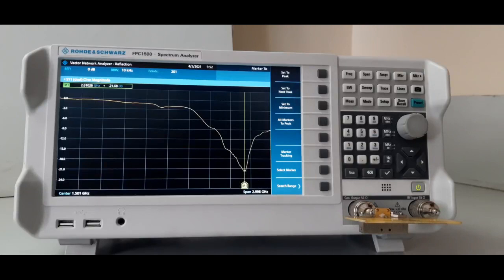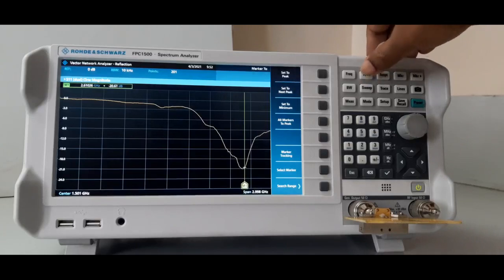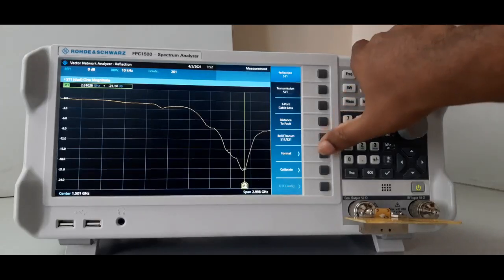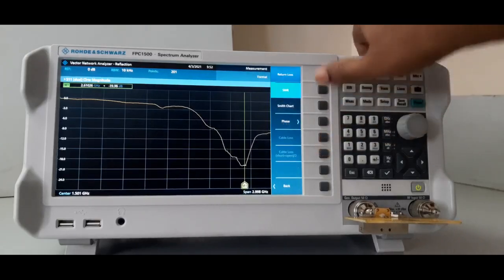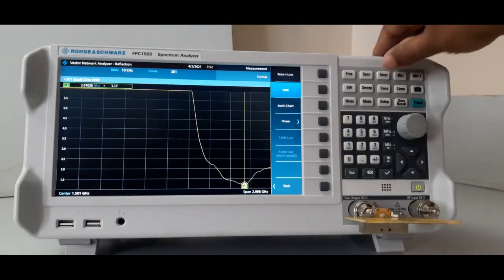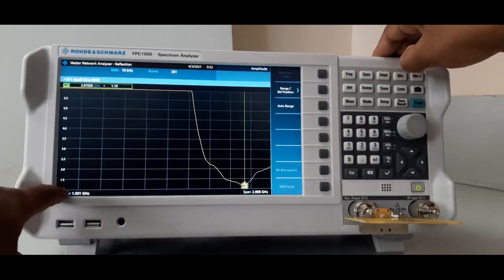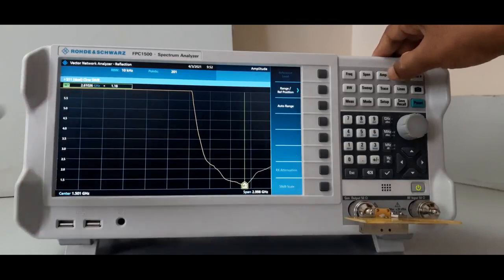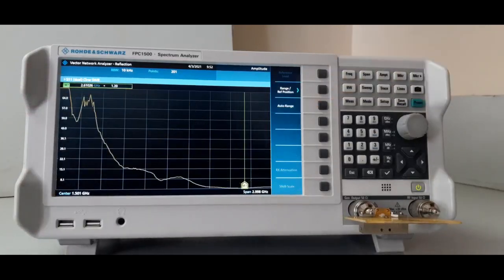Next is I will check VSWR for the same antenna. Go to measurement, go to measurement format VSWR, and range also you select. Now it is 1.1 to 5.5. I will give auto range.